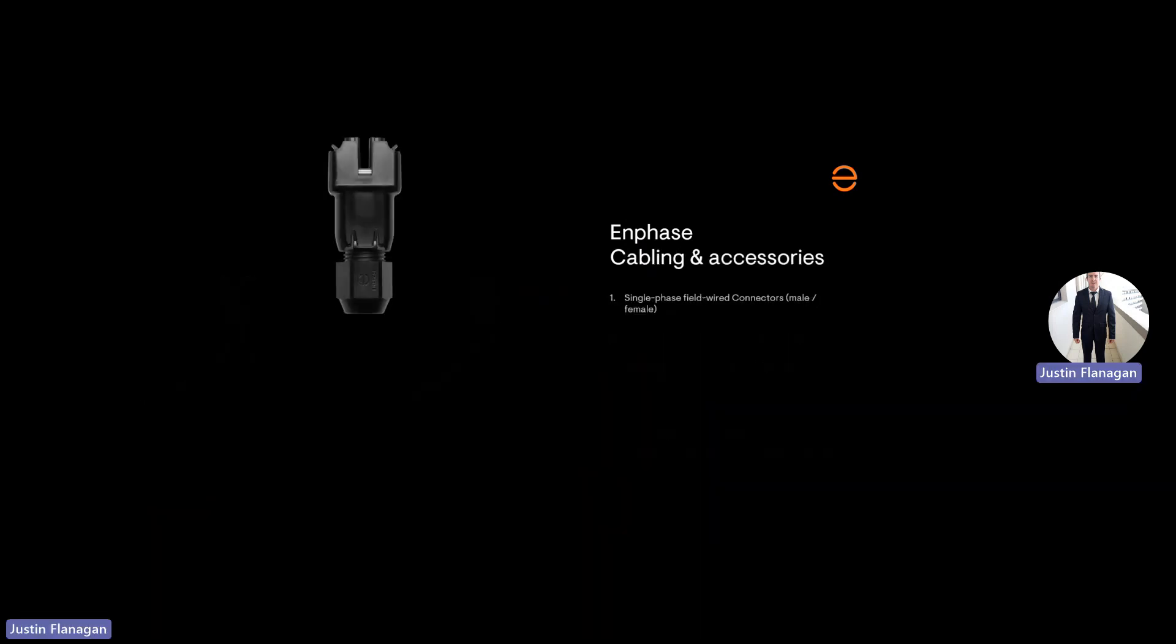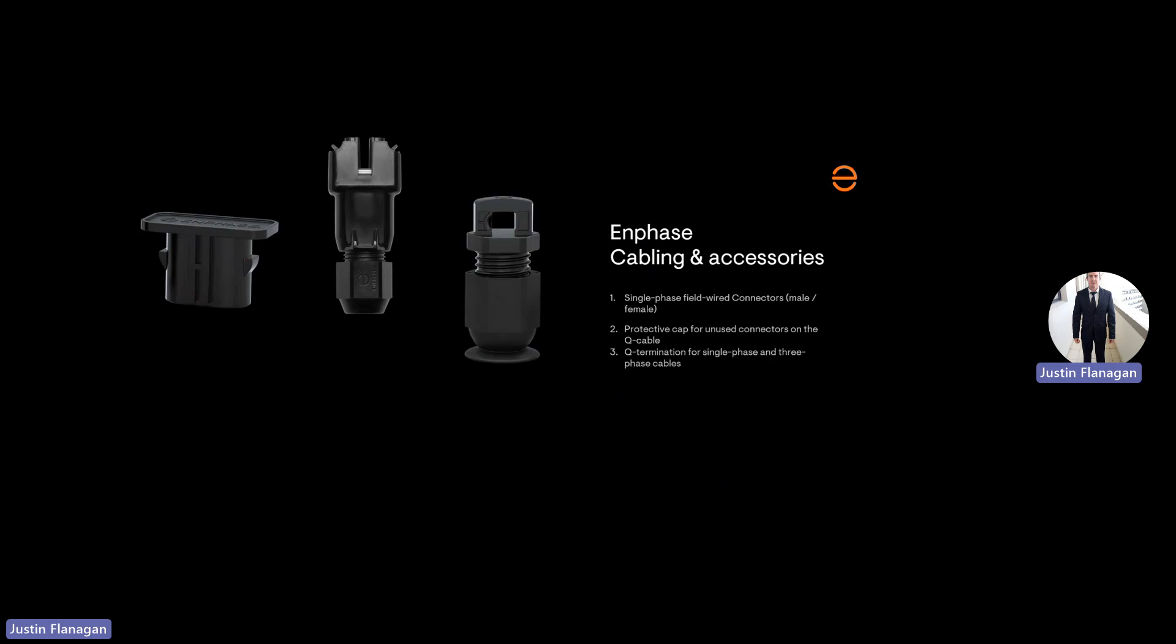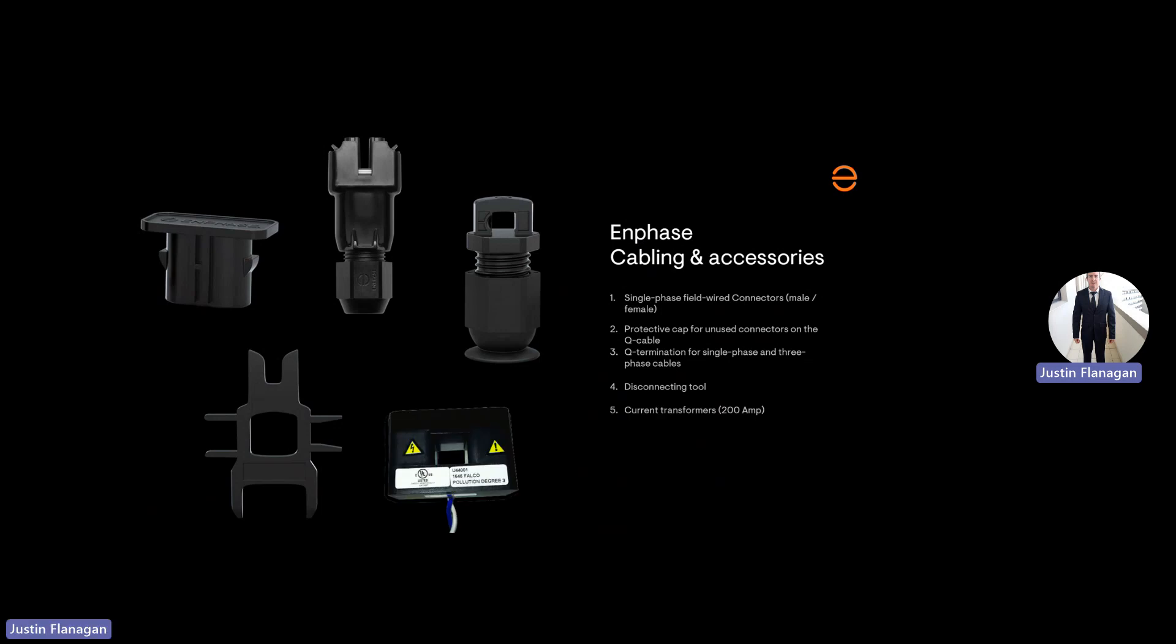We'll go through the accessories. This is the field wireable connector, you get a male and female, only used for single phase connection. You've got your protective cap for unused AC connection on your IQ cable, your IQ termination for single phase and three phase to put on the end of your cable, your tail on your branch circuits so no water or dust can get inside and to protect that there are no live circuits on your roof. You've got your disconnecting tool to disconnect your DC connector from the microinverter or your AC IQ cable from your microinverter. And you've got your current transformer that can handle 200 amps, connected directly to the gateway.